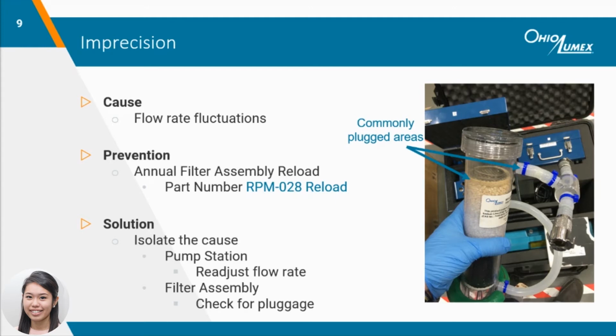If the fluctuations still occur when the filter assembly is disconnected from the pump station, then reduce the flow rate set point on the mass flow controller by 1 liter per minute and slowly increase back to the original flow rate. If that does not work, the pump station will need to be sent back to Ohio Lumex for further troubleshooting.